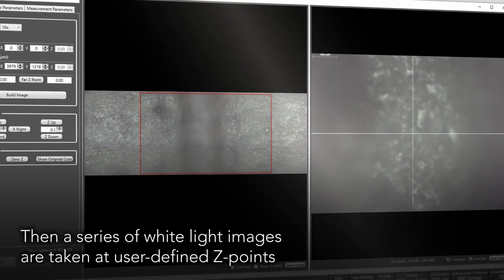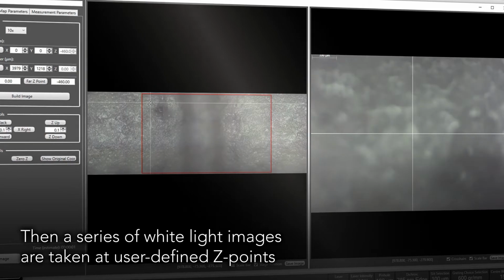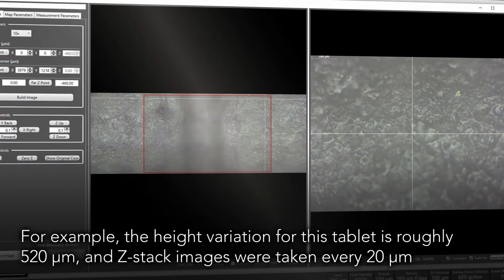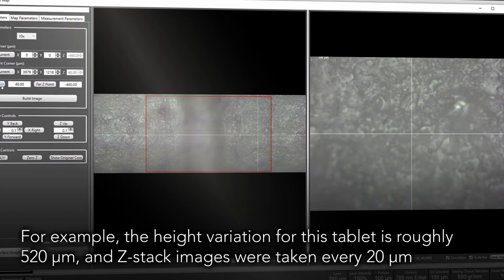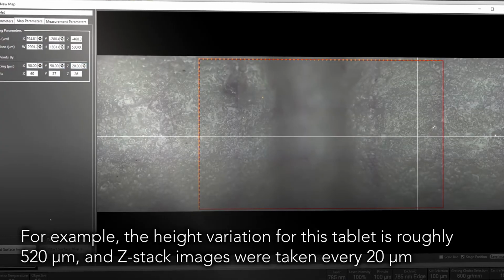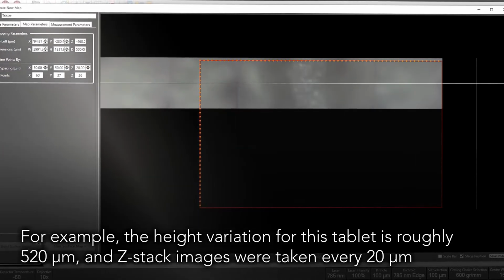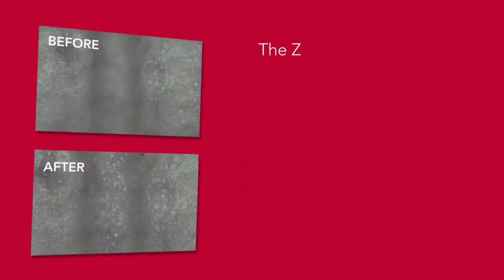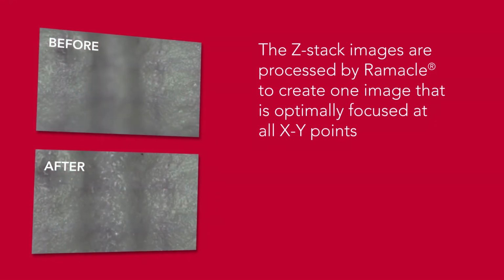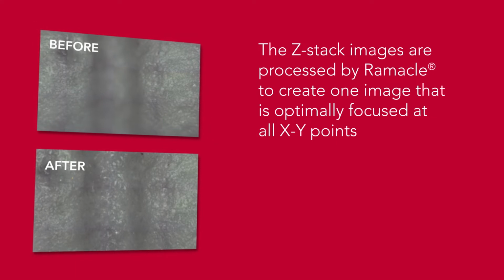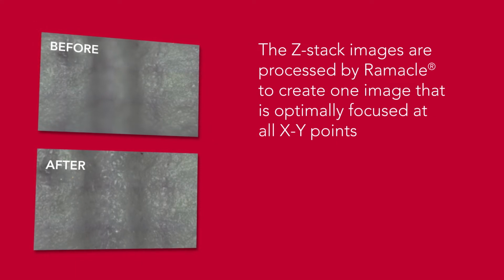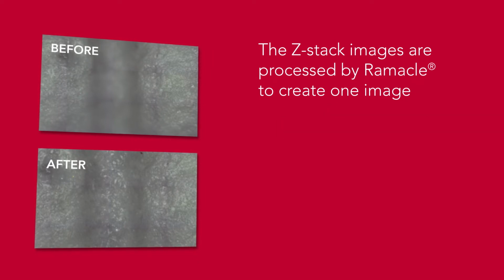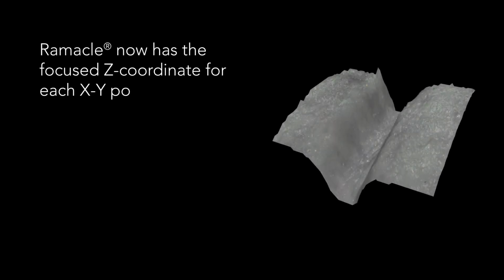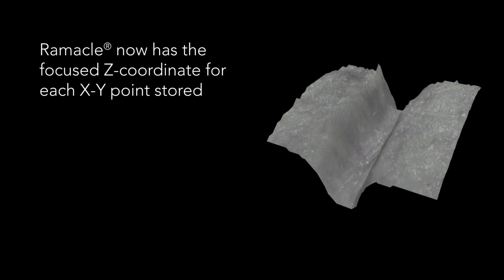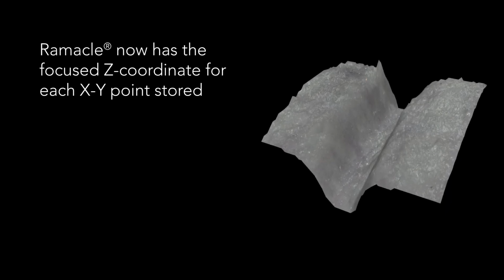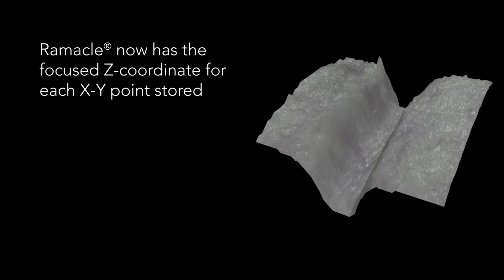The user then defines their Z resolution, and a series of white light Z stack images are taken. For our pharmaceutical tablet, the height variation of the surface is 520 microns, and Z-stack images were taken every 20 microns. These Z-stack images are processed in Ramacle, creating one image that is optimally focused at all XY points. Ramacle now has the focus Z coordinates for every XY point stored, and we can view our surface image in 3D topography view.